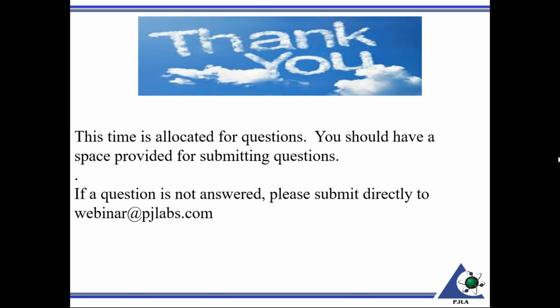And I'm a calibrator, and I don't want to steer anybody wrong. I have some specific technical questions in regard to testing. Just based on this presentation here, this person is asking, they're a testing lab, not a calibration lab. What is the best way to determine the uncertainty of the internal test method? So I'm assuming you wrote your own test method. Is it sufficient to do a repeatability study based on 2 or 3 replicates, 3 or 4 times, and then use a different standard deviation to calculate the uncertainty for the test method?